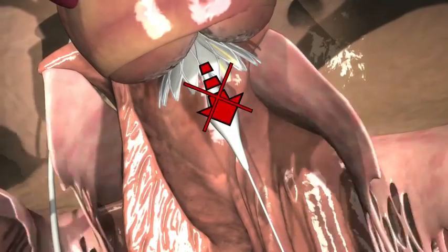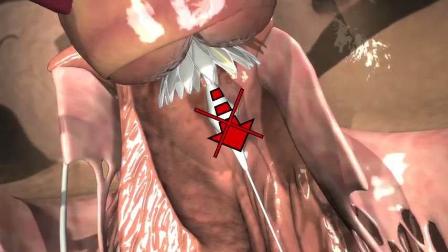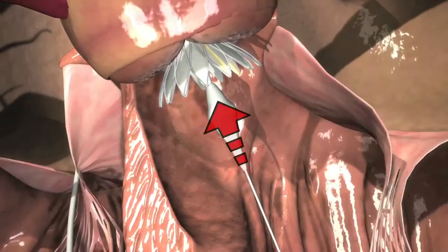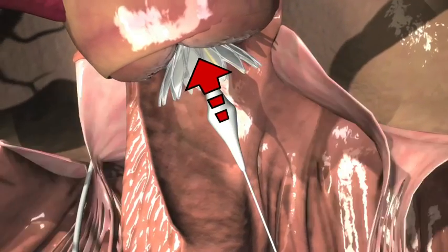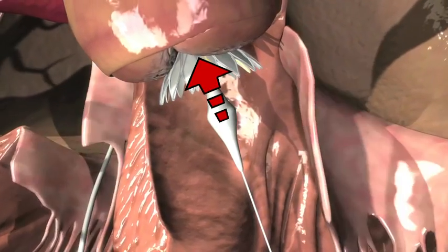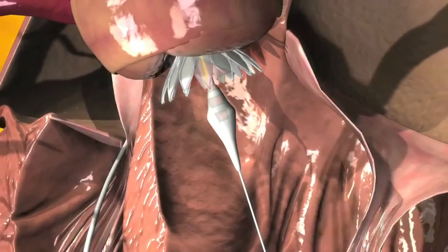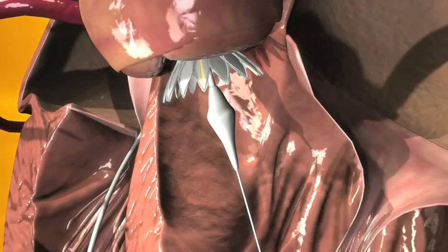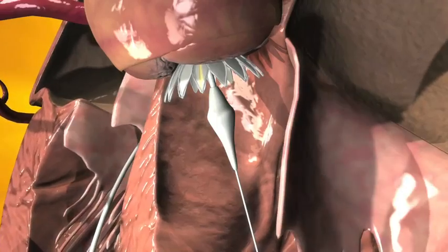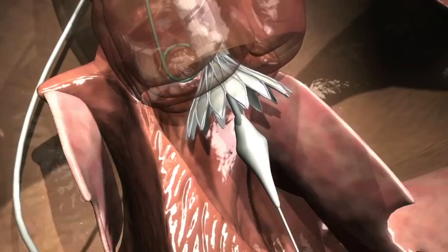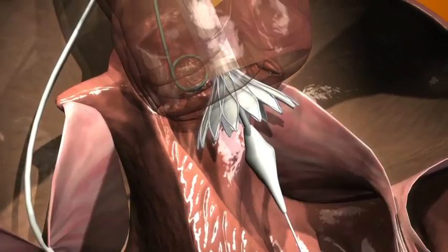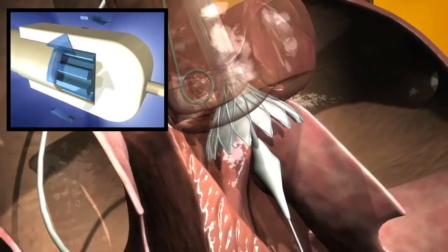As the inflow aspect of the valve starts to flare outwards, monitor valve position under fluoroscopy. Note: once annular contact is made, the frame cannot be safely advanced into a lower position. It can, however, be repositioned in the antegrade direction if the frame has been deployed less than or equal to 2/3 of its length. Careful assessment of frame position relative to the annulus is highly recommended for optimal implantation. After evaluation of valve position is achieved and adjusted at this stage, continue to deploy the 2/3 deployment.